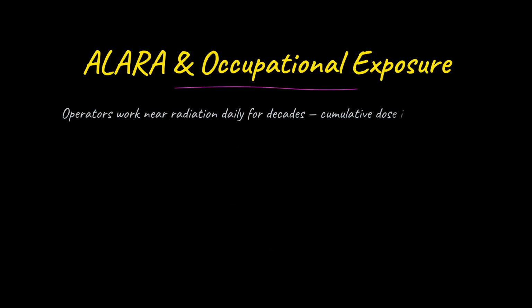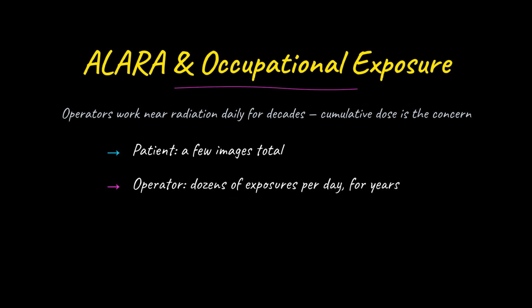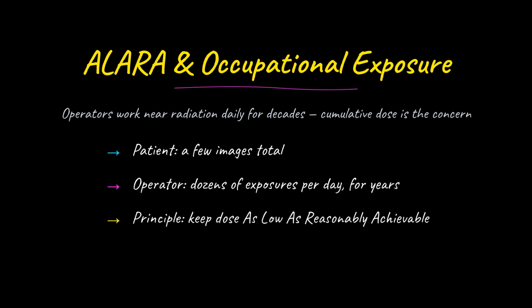Unlike a patient who receives just a few images, an operator may stand near the equipment dozens of times a day for an entire career. Small repeated doses accumulate, so the guiding principle is ALARA, as low as reasonably achievable. Note that the lead apron shields the patient. The operator relies on distance and the room barrier.